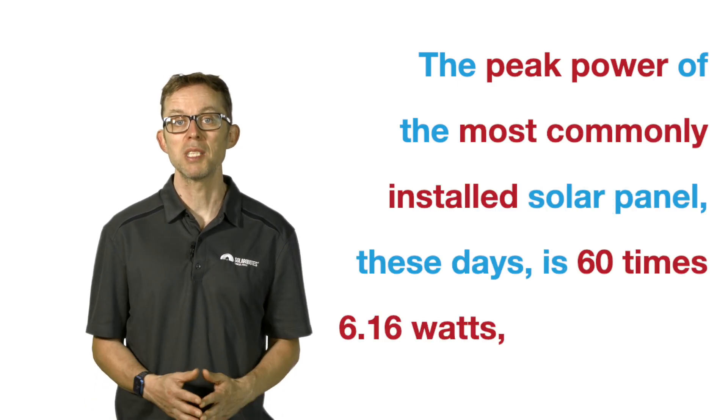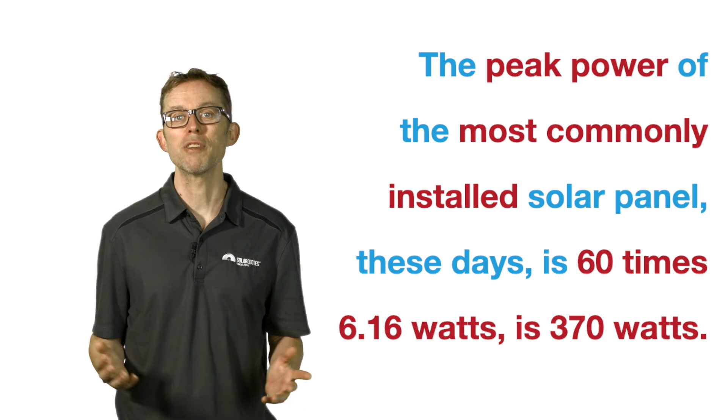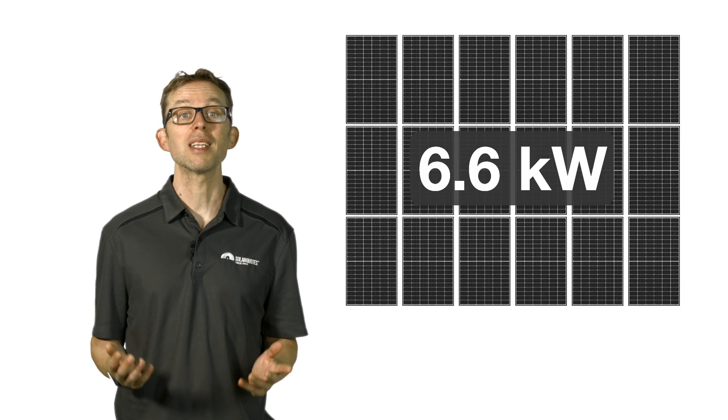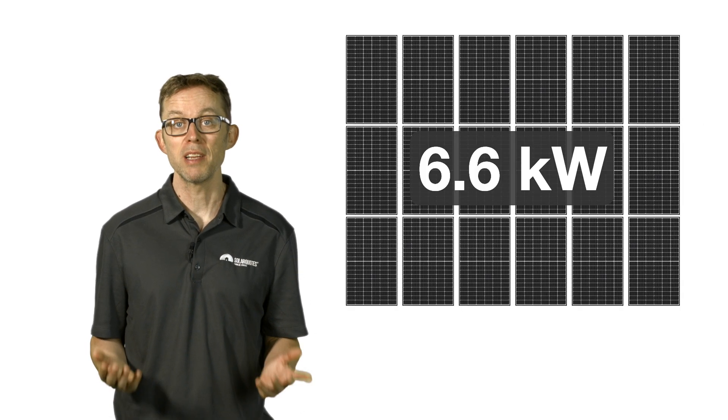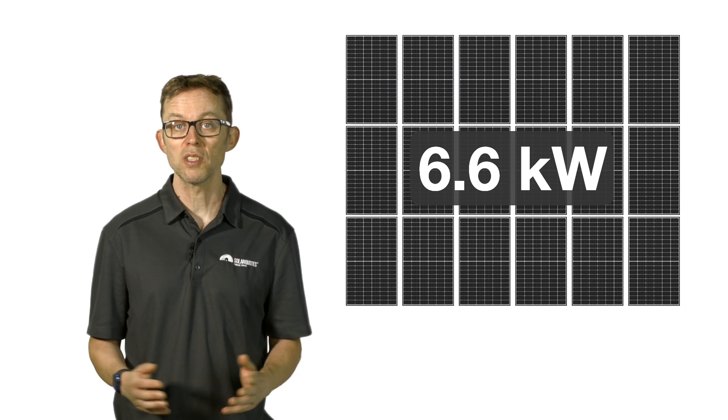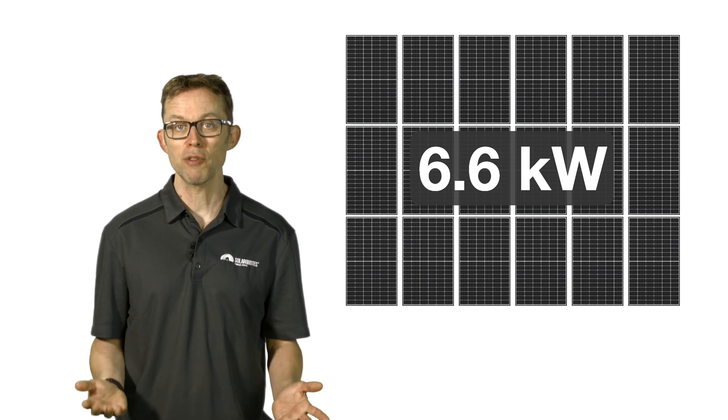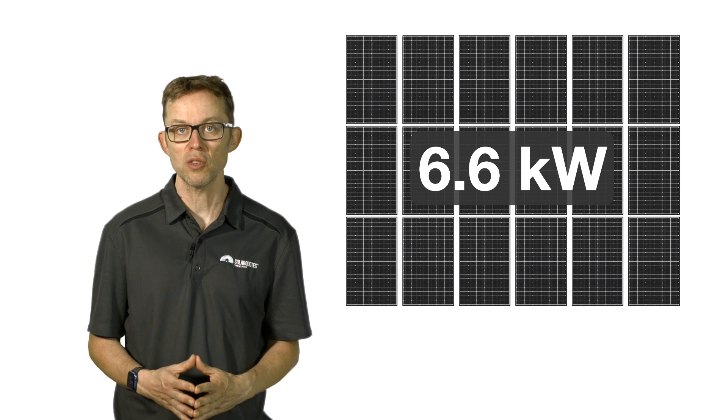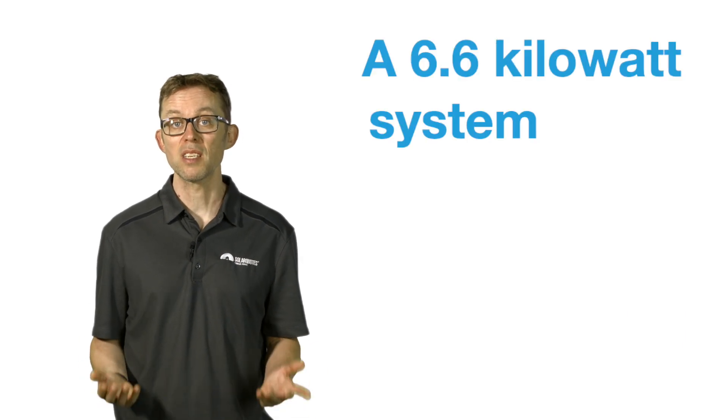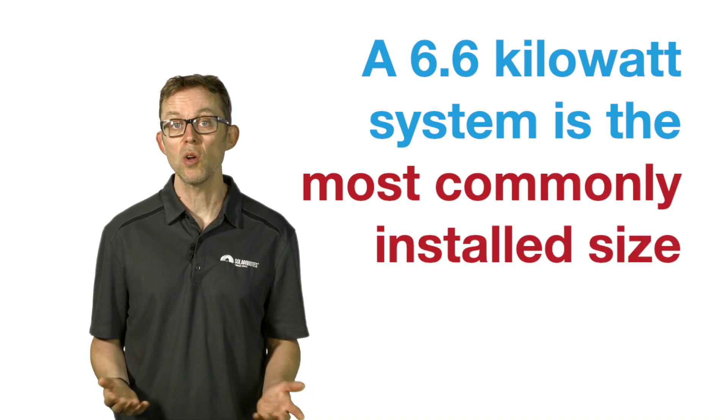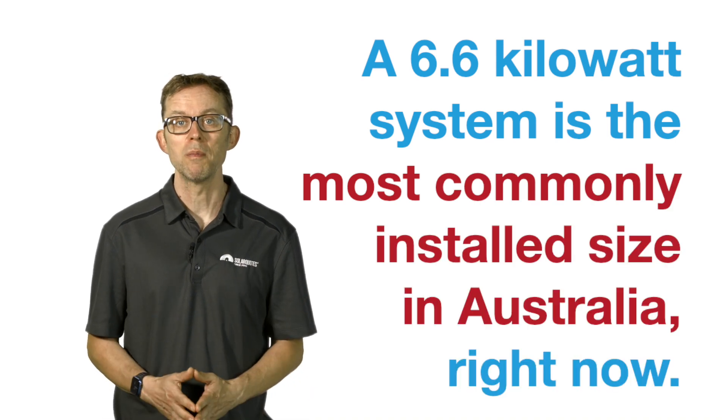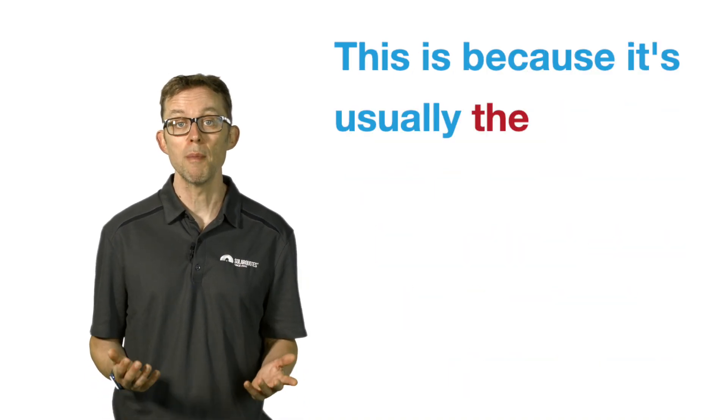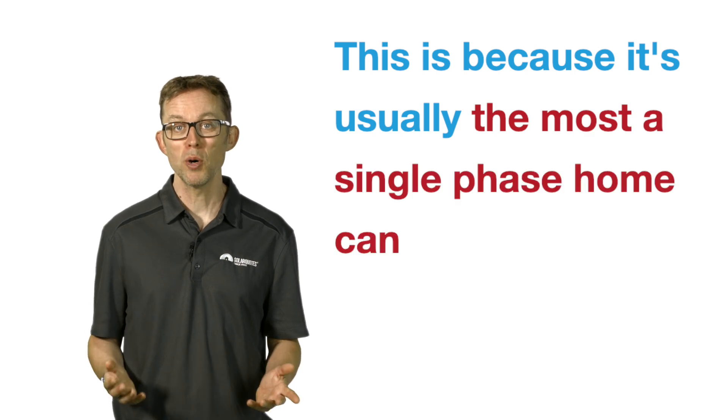If you connect 18 of these panels together, you have enough for a 6.6 kilowatt solar system. 18 times 370 watts equals 6,600 watts, equals 6.6 kilowatts. A 6.6 kilowatt system is the most commonly installed size in Australia right now. This is because it's usually the most a single-phase home can put on without needing export limiting.